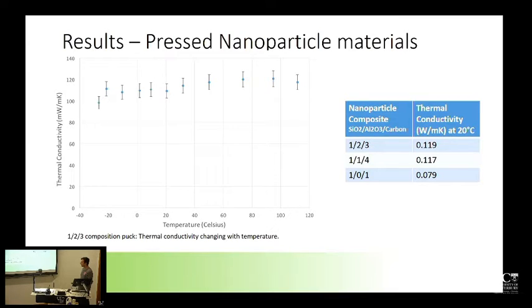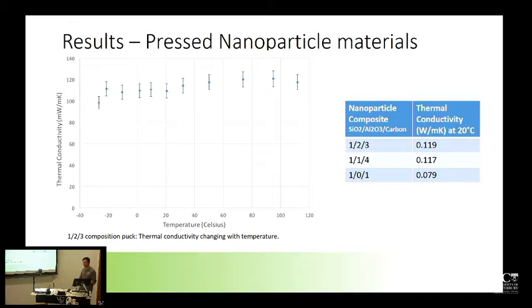I wonder whether that test methodology is unsuitable for the material, given that carbon is sort of a radiation suppressor. It is absolutely lamp black when you look at it. And I wonder if there is some reason that they weren't getting any signal out the other side of that laser flash calorimeter. Because they made a larger tile and measured that with a guarded heat calorimeter, the same that Callahan Innovation measured it with, and they got a value which was almost exactly what I'm measuring here. So I wonder whether their numbers are correct on that or not.